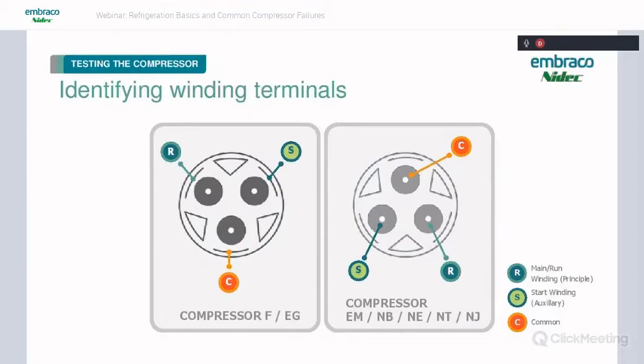On your F and EG models, you're going to have the common on the bottom. And try to remember to go clockwise from common. So common's going to be on the bottom. Going clockwise to the top left, you have your run winding. And then top right, you have your start winding.